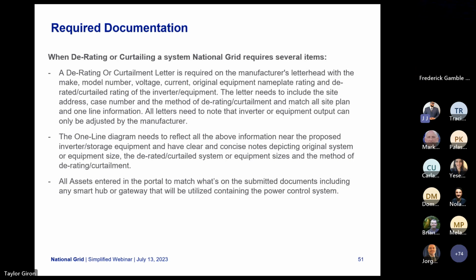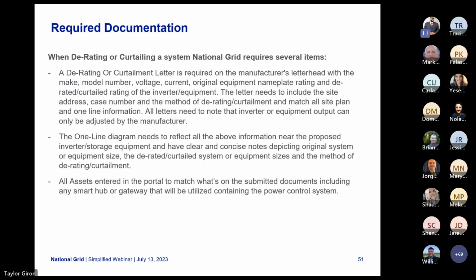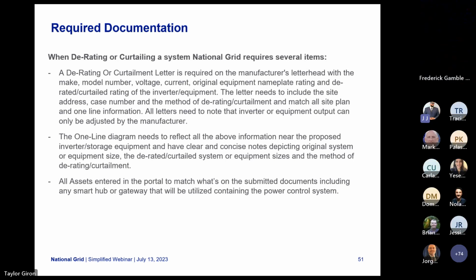Most of this information is already reviewed on one-line diagram submissions, but needs to be included with the additional derating or curtailment notes near the proposed inverter or storage equipment. There also needs to be clear and concise notes depicting original system or equipment size, with the derated or curtailed system size, and any equipment export changes with the method of derating or curtailment. And lastly, all of our proposed assets entered into our portal need to match what's on all the submitted documents. It's for accuracy purposes and to make sure that the aggregate sizes match up for all the systems progressing. This is going to include any smart hub or gateway utilizing a power control system that's going to be utilized as a site limiting protective function.